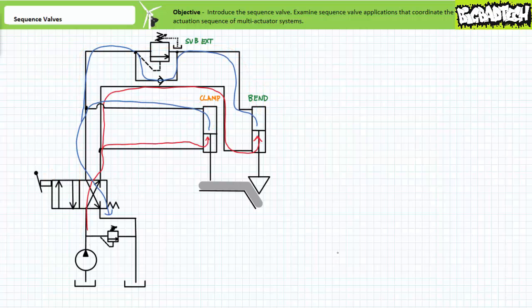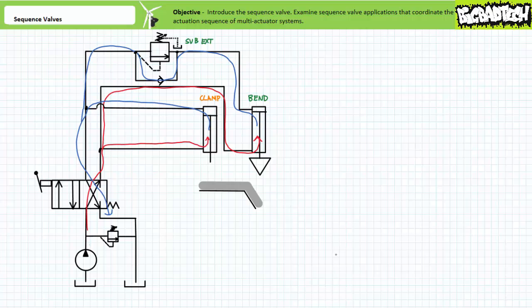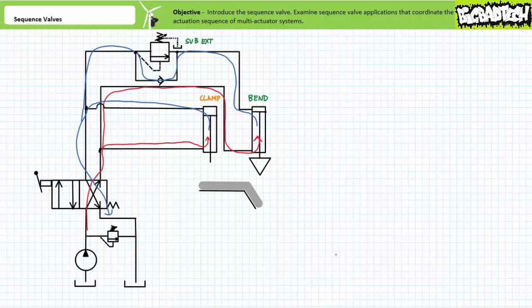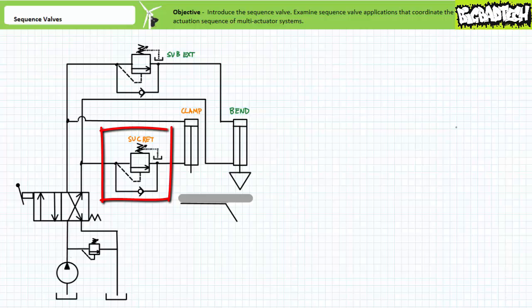When the directional control valve is shifted to the cross connect position, the check valve bypass bypasses the sequence valve and allows the bend cylinder to retract with no pressure precondition. Note that during retraction, both cylinders are placed in parallel with one another, and sequence of retraction is pressure dependent. While suitable for some applications, this might not be the most desirable scenario if we wanted to ensure the clamp cylinder maintained the workpiece secure while the bend cylinder retracted, and then retract the clamp cylinder as a final step.